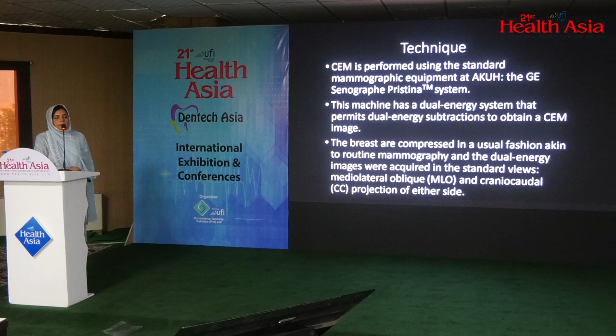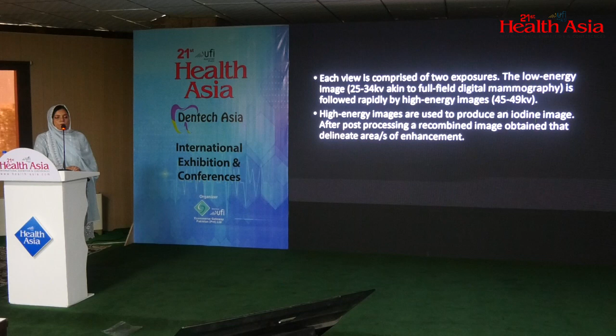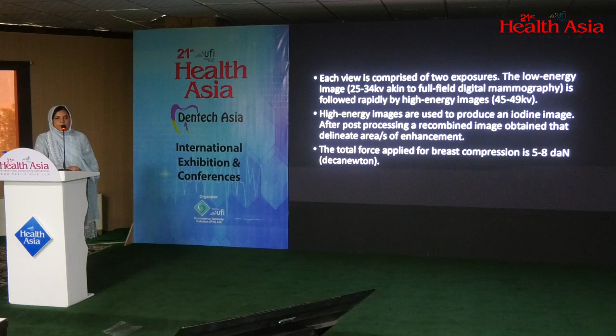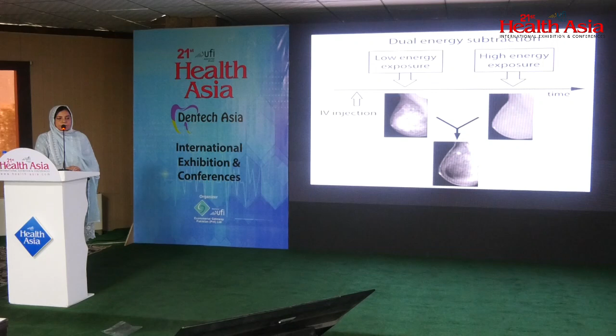Each view is comprised of 2 exposures. The low energy exposure image, 25 to 34 kV, akin to FFDM, is followed rapidly by a high energy image, 45 to 49 kV. High energy images are used to produce an iodine image. After post-processing, a recombined image is obtained that delineates area or areas of enhancement. The total force applied for breast compression is 5 to 8 Newton, as we use in routine mammography. A complete examination takes 5 to 6 minutes to perform.